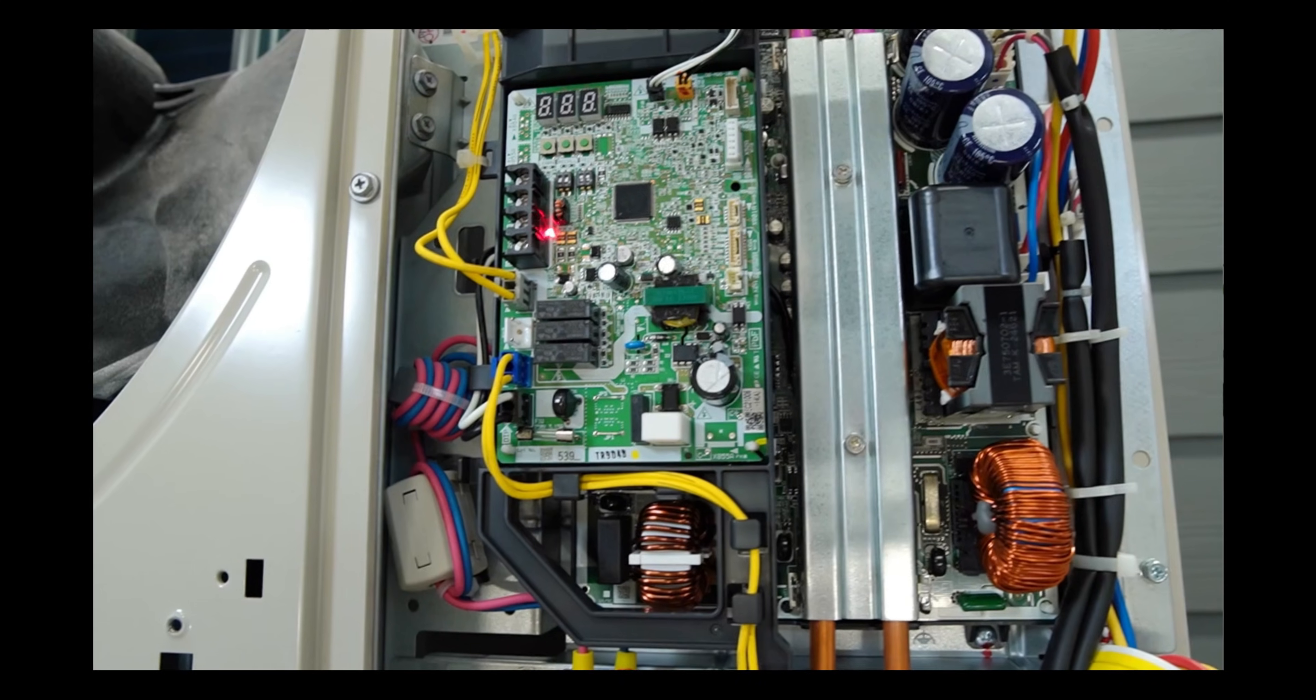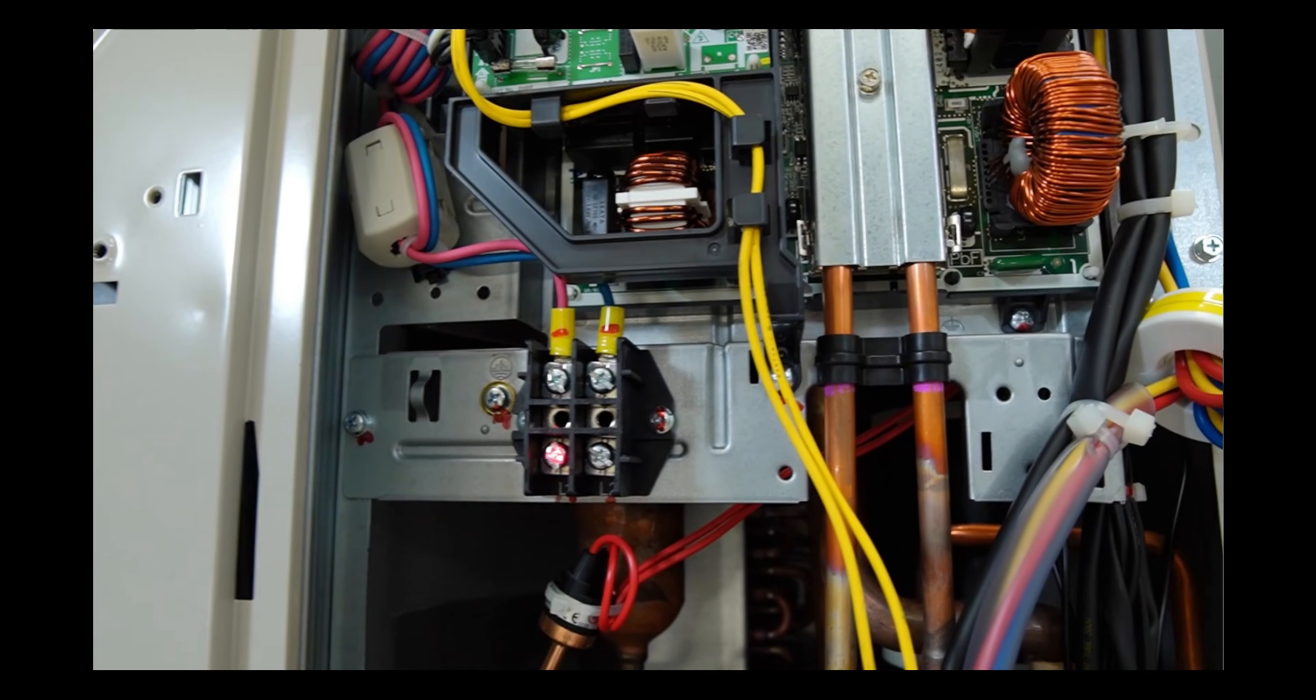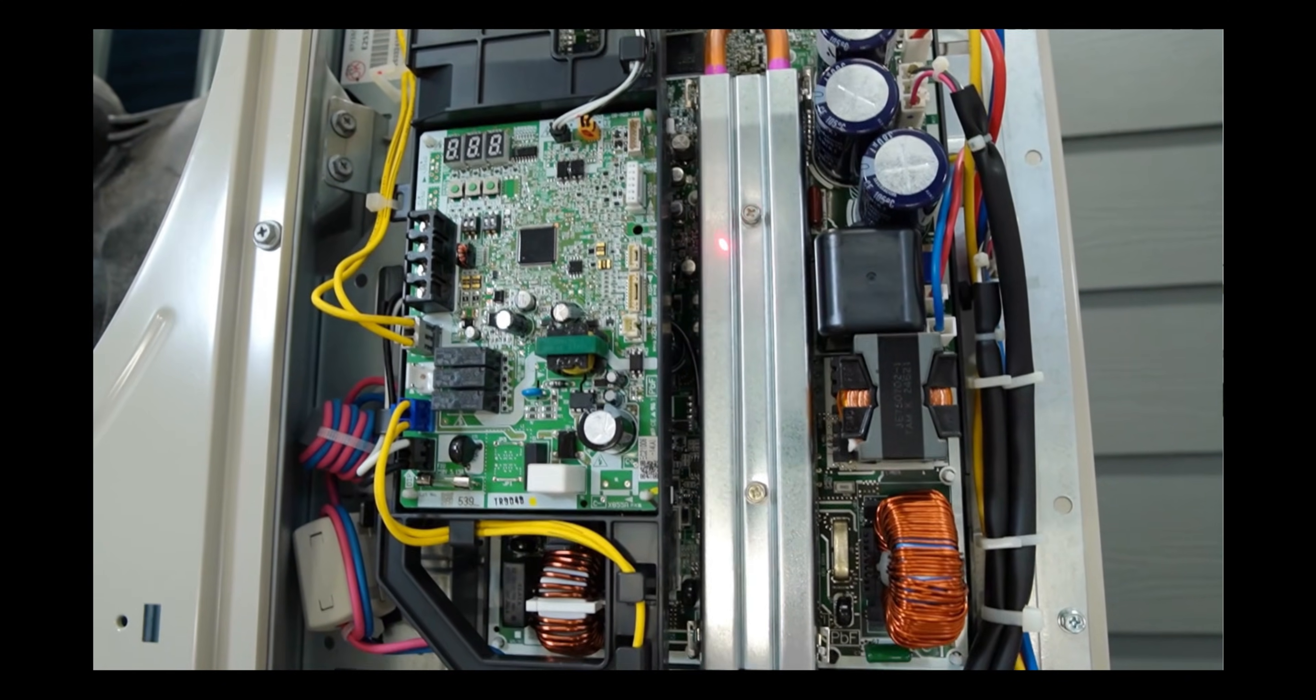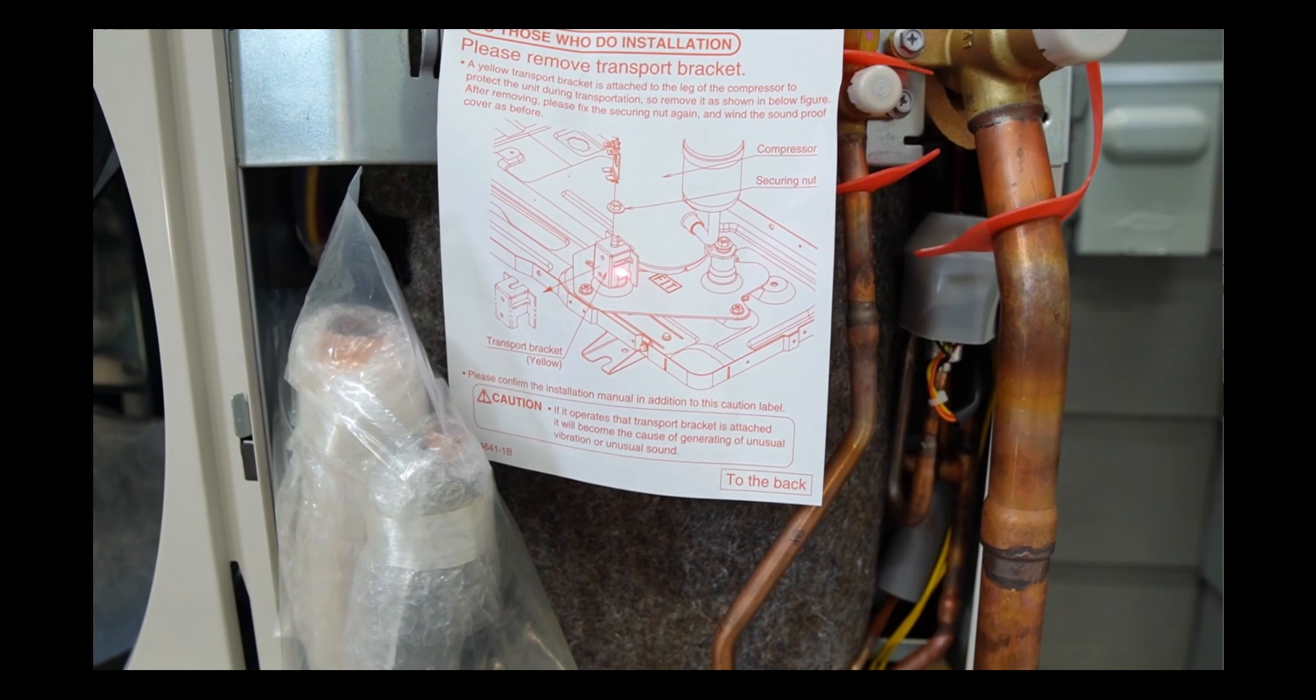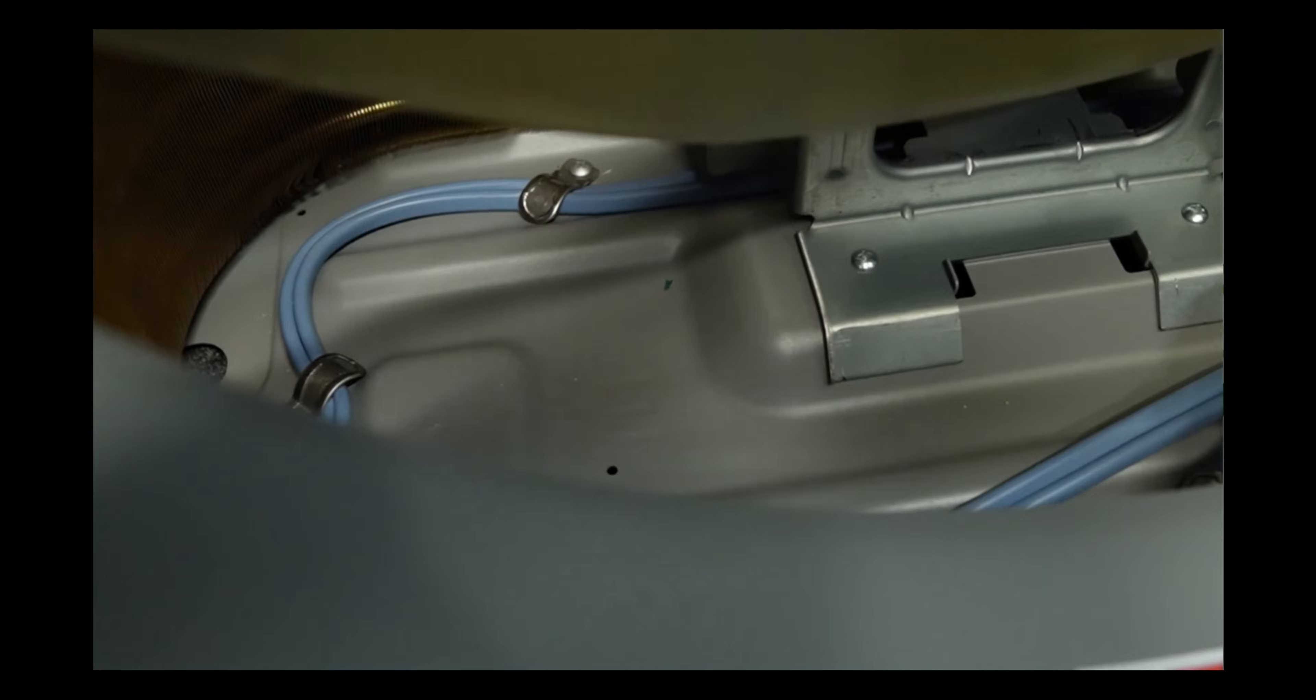This one is the communication board, and this one is the inverter board. The communication terminal on this condenser only requires two wires, and we have the main power here, L1 and L2. Now to keep the inverter board cool during the hot summer, Daikin has added a refrigerant cooling loop here. The heat pump is actually shipped with a compressor bracket that needs to be removed before installation. If somebody forgets to remove it, it's probably going to make a lot of noise. Here we have extra refrigerant lines and the liquid line dryer down there. The bottom plate heater is a setup that I never seen before, and I thought it was incredibly clever. They added this hot refrigerant loop to prevent ice from building up in the bottom plate. What I've seen so far is that most manufacturers use resistant heat to prevent ice buildup on the bottom plate.